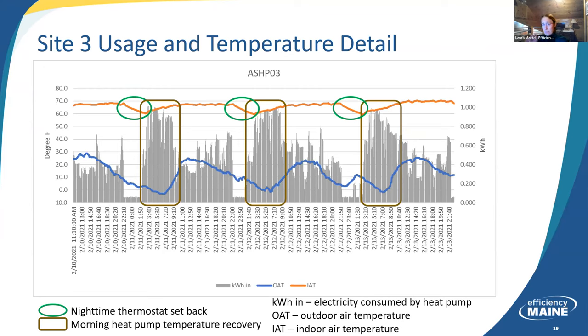And then when the system wakes back up and says, oh wait, we need to go back up to daytime temperatures, you can see it climb, and fairly slowly. Heat pumps are slow heat. They're not fast heat, right? It's like slow money and slow food. Sometimes it's good to wait for things. So heat pumps are slow heat. They're not a furnace. They're not going to blast you with ridiculously hot air. They're just going to creep up the temperature over time.